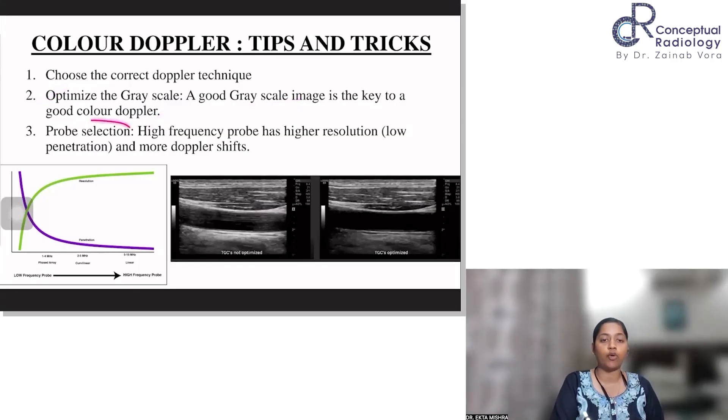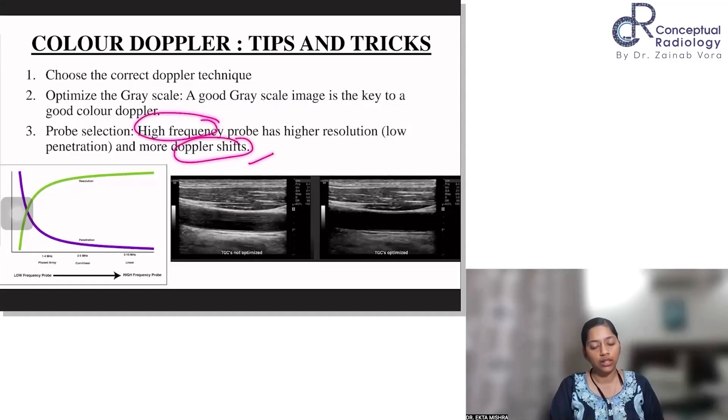So starting with probe selection. You have a high frequency probe and a curvilinear low frequency probe. Higher frequency probes have relatively higher resolution and therefore they have low penetration because the sound waves get attenuated. So due to their high frequency, they have more Doppler shifts and better Doppler ultrasound. As the penetration decreases, your resolution improves. But these are inversely related. So low frequency probes have higher penetration but poor resolution and vice versa.